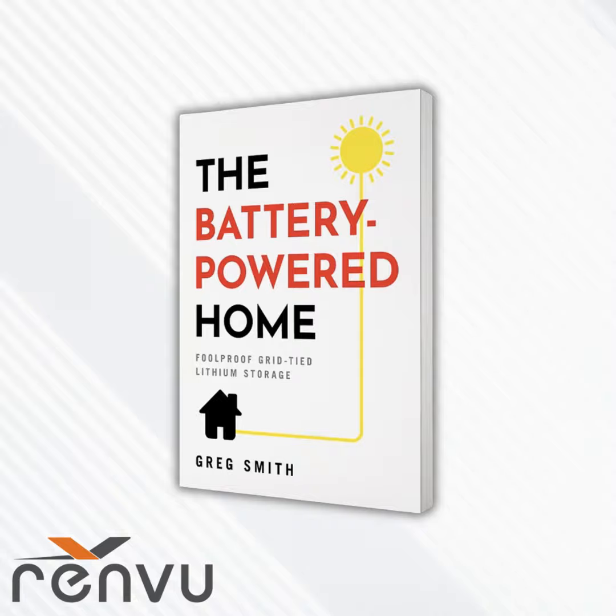So if all you want is backup, a generator is a cheaper way to go, as long as you have fuel. The beauty of a complete energy storage system is you have the solar and the batteries, you're saving money on your utility bill throughout the year, and when times get tough, you have your energy storage system to get you through. That means you only need a small generator for times when there's not enough sun to charge the batteries, or when you have larger loads the battery system can't handle for long—you just start the generator up.